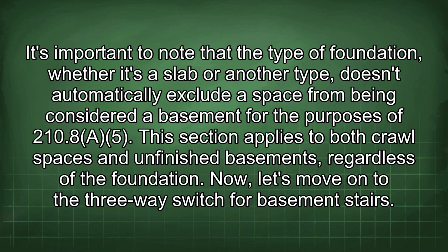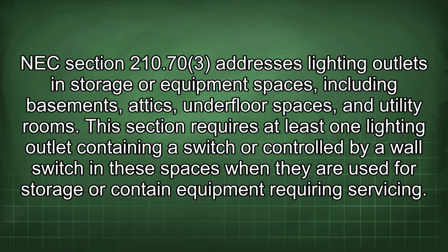Now, let's move on to the three-way switch for basement stairs. NEC Section 210.70(3) addresses lighting outlets in storage or equipment spaces, including basements, attics, underfloor spaces, and utility rooms. This section requires at least one lighting outlet containing a switch or controlled by a wall switch in these spaces when they are used for storage or contain equipment requiring servicing.